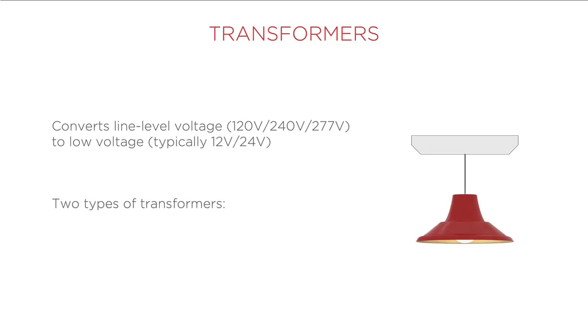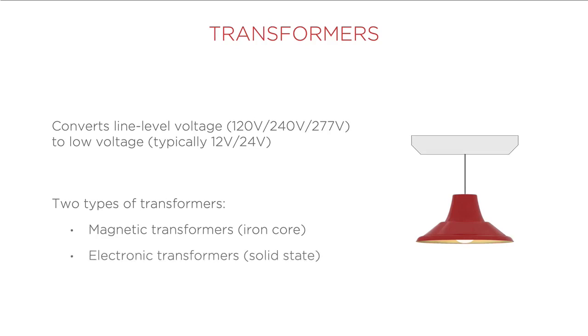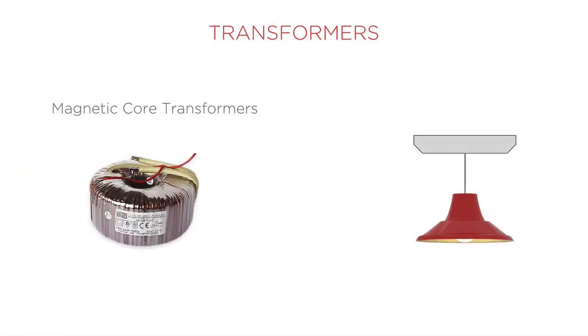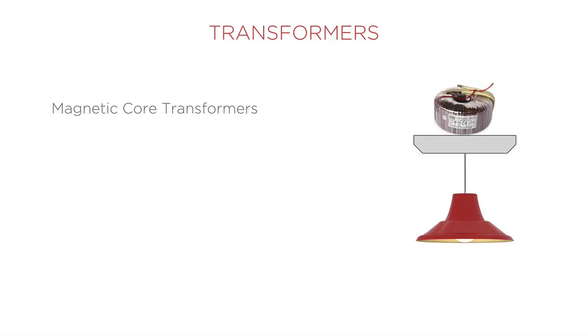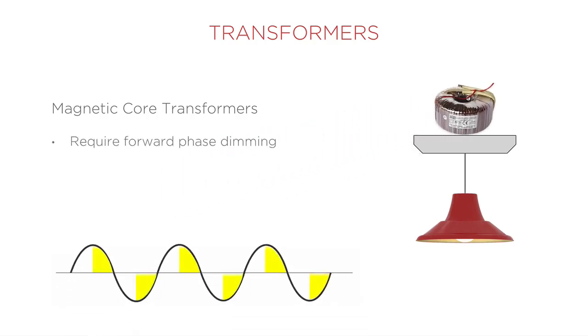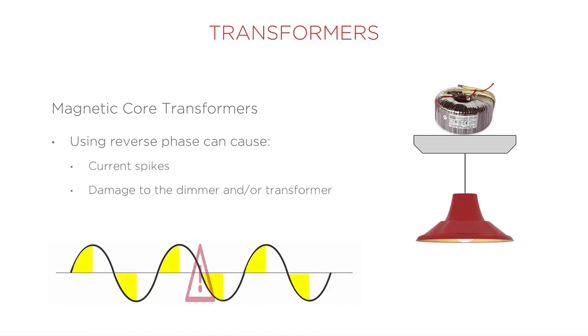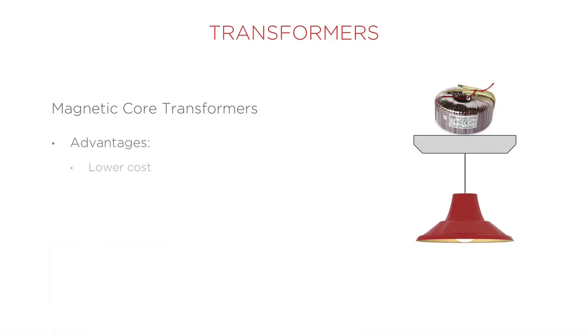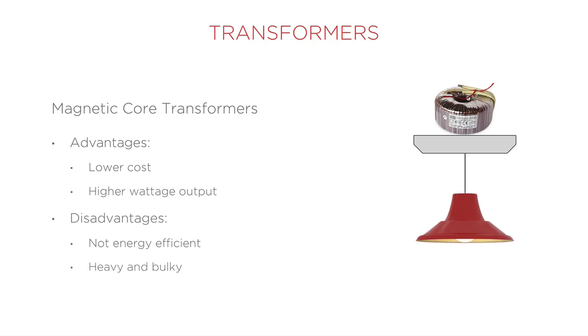There are two types of transformers: magnetic core transformers, or iron core transformers, or the newer, more efficient, electronic state or solid-state transformers. Magnetic core transformers are the older of the two transformer types. They are required for forward phase dimming. If used with reverse phase dimming, it could cause current spikes and damage to the dimmer and/or the transformer itself. It is a lower cost and has a higher wattage output, but is not nearly as energy efficient, and the transformers themselves are heavy and bulky.